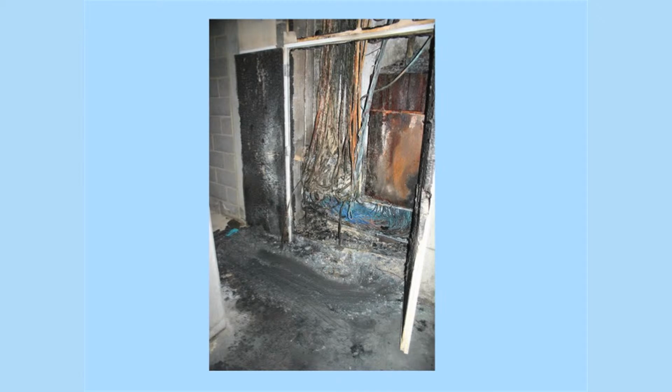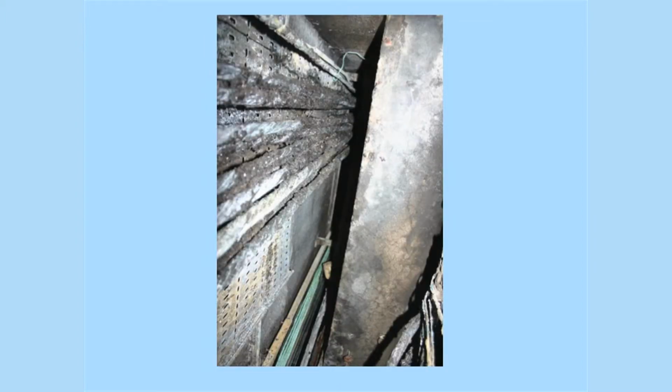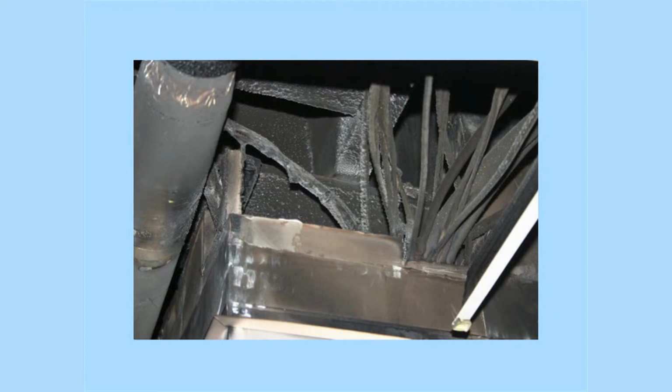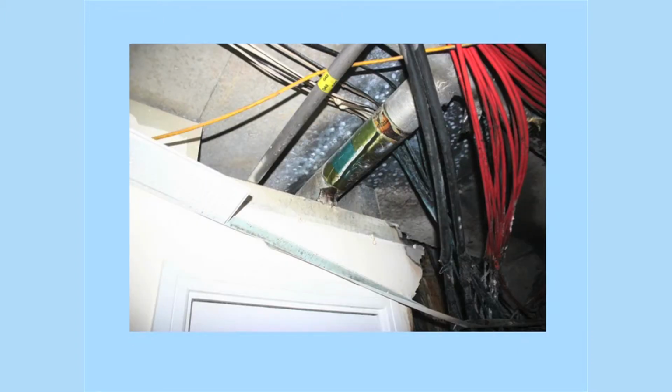Unfortunately, where such precautions are not put in place, fires can spread very rapidly on large bunches of PVC insulated cables, and spread quickly up the riser, as I've indicated, and then into the void space above the common passageway, which, because of the enormous quantities of smoke that are produced, can impede means of escape. And here we see cables emerging from the top of the cupboard straight into the ceiling void. And they're an example of the gas pipe in similar vein.